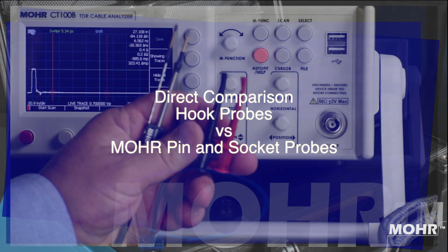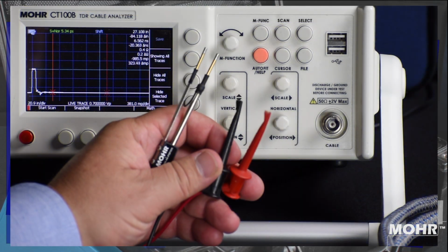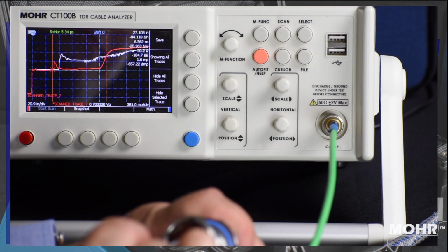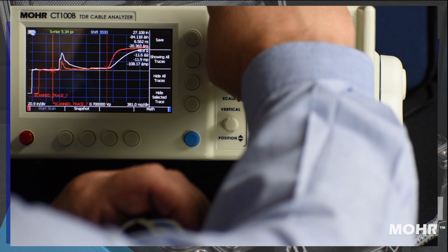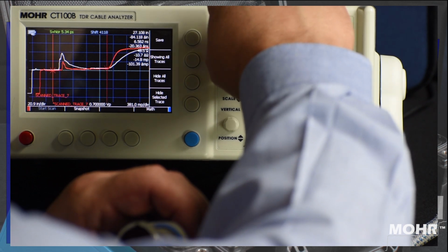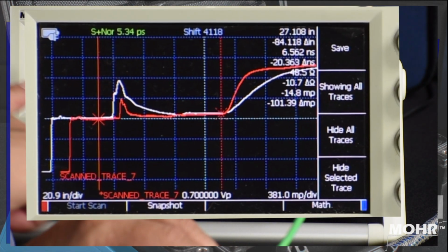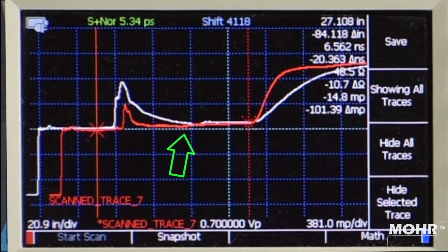Comparing the hook probes to the pin and socket set, as I line up the traces to match time, you can see that the trace from the hook probes is severely distorted in the first half of the cable being tested. It would be difficult to see if there were any defects in that portion of the cable compared to the trace using the pin and socket probes.